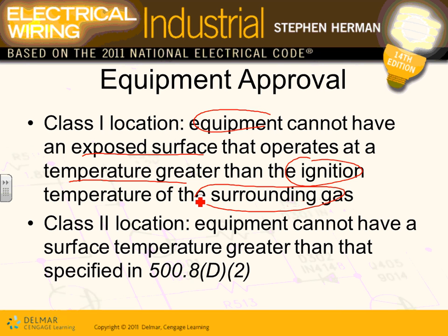That's number one. Number two, it doesn't allow the gas to enter the enclosures. So when you flip the switch and you start a little arc, you have an explosion. So it seals the arcing and sparking equipment. It doesn't allow the gas and the vapor to get into it, number one. And number two, the surrounding gas doesn't get hot enough to ignite the surrounding. So that's your class 1 location.